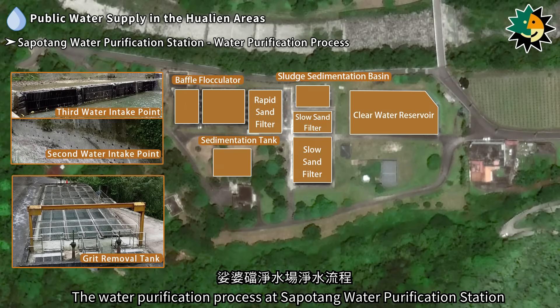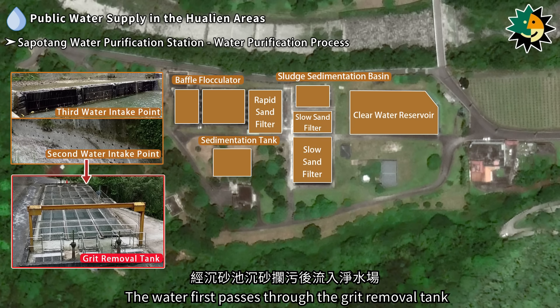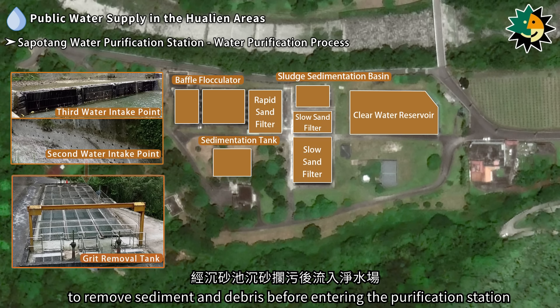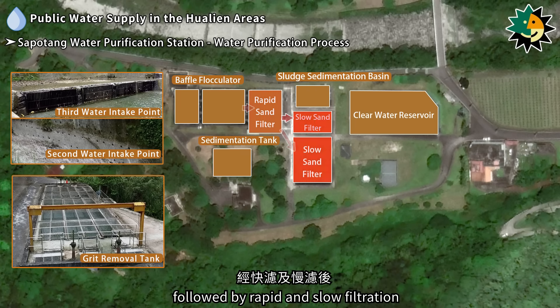The water purification process at Sapotang Water Purification Station involves drawing raw water from the second and third water intake points. The water first passes through the grit removal tank to remove sediment and debris before entering the purification station. It is then sent through the baffle flocculator into the sedimentation tank, followed by rapid and slow filtration.